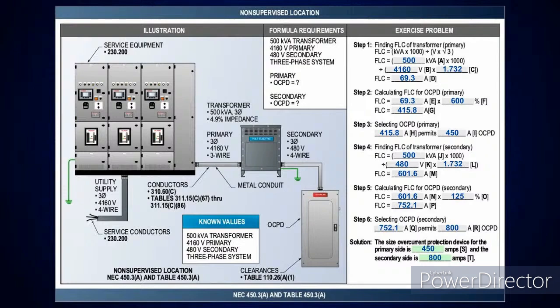Okay? Now, a lot of people look at this, but you're going to look at that secondary protection, and you're going to notice I'm 1,000 volts or less here. I got a 480 volt secondary, so I'm going to go all the way to the far right-hand side of the column, and it's going to tell me to take it at 125%. I have a superscript 1, so I'm going to go up to the next standard size. So I'll take the 500,000, divide it by 831 volts, going to give me 601.6 amps times 125%. Gives me 752.1 amps. Go to table 240.6(A), the next standard size above that's 800 amps.